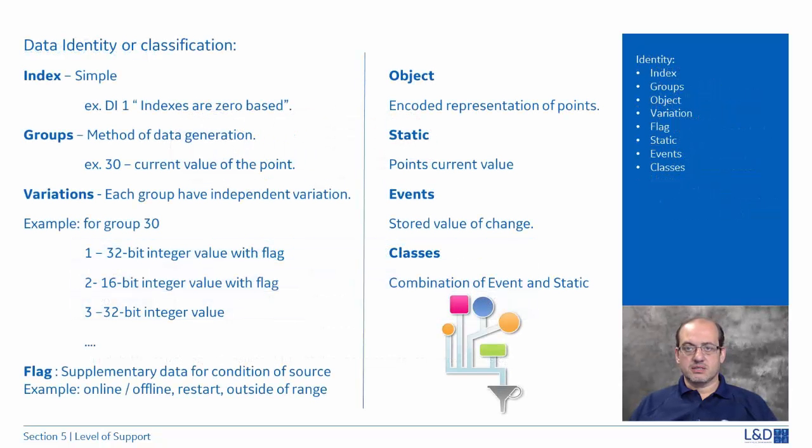One of the key things in communication in DNP is how do we refer to the data that's being generated: a voltage measurement, a current measurement, a status of a breaker. All of this information that is available in our substations is basically translated into digital data, either a digital input or a digital output, an analog input or an analog output, a counter, or a status of a device. And this information is referred to with an index. So the data has an index.